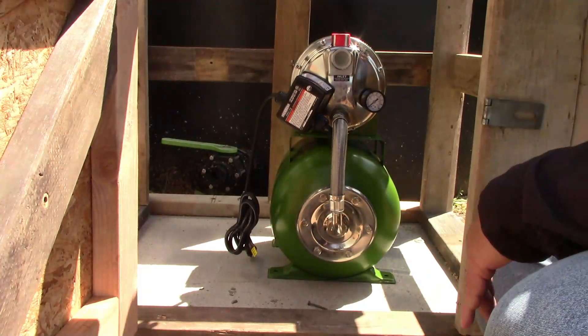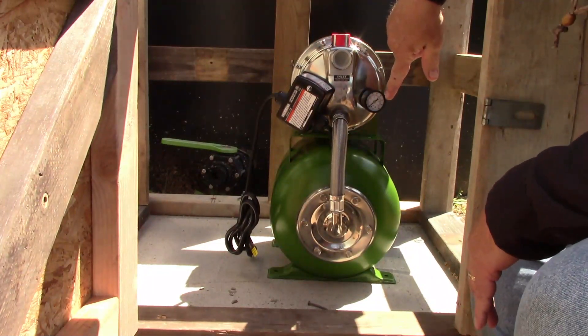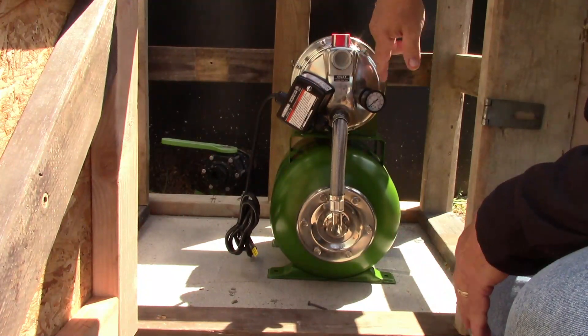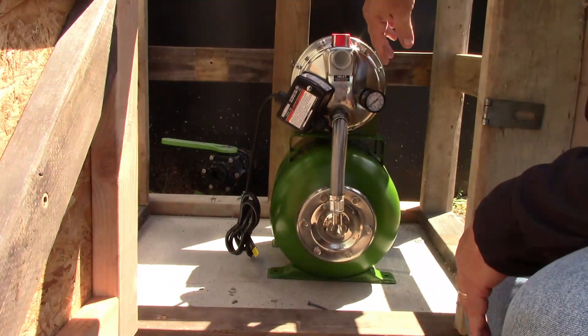It's a pretty nice little pump. It already has its pressure switch and it's wired for 110 volts, and it comes with a pressure gauge. It's supposed to cut on at 30 PSI and cut off at 50 PSI, which is a good range for watering or anything like that.